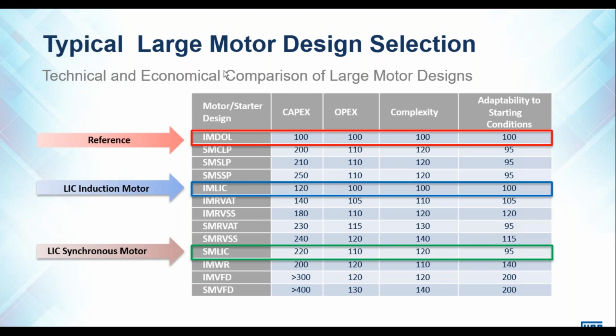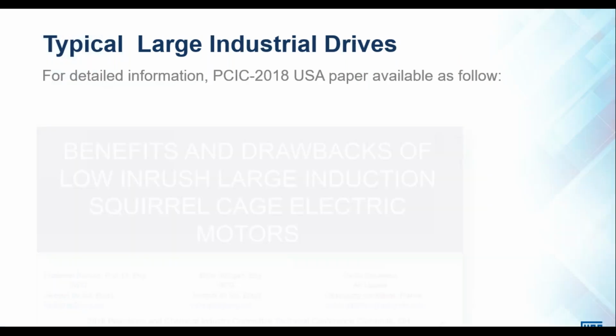Then our last comparison would be against capex, opex, complexity, and adaptability to starting conditions. Again, we use the induction motor direct online as our reference, and we can see that a low inrush current design motor is approximately 20% more in the case of capex. Opex is pretty much the same, as with complexity and adaptability to other starting conditions. A synchronous machine of similar design would be more than double the capex. Opex would be slightly more. It is a much more complex machine, and it has a little bit less adaptability to starting conditions.